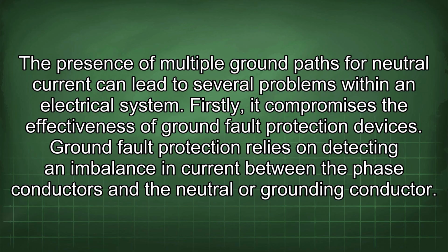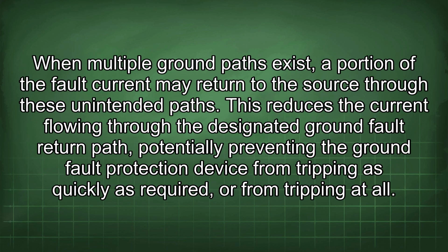The presence of multiple ground paths for neutral current can lead to several problems within an electrical system. Firstly, it compromises the effectiveness of ground fault protection devices. Ground fault protection relies on detecting an imbalance in current between the phase conductors and the neutral or grounding conductor. When multiple ground paths exist, a portion of the fault current may return to the source through these unintended paths. This reduces the current flowing through the designated ground fault return path, potentially preventing the ground fault protection device from tripping as quickly as required, or from tripping at all.